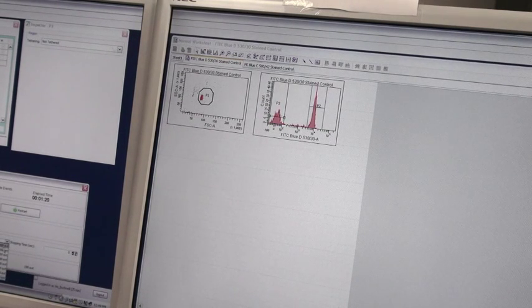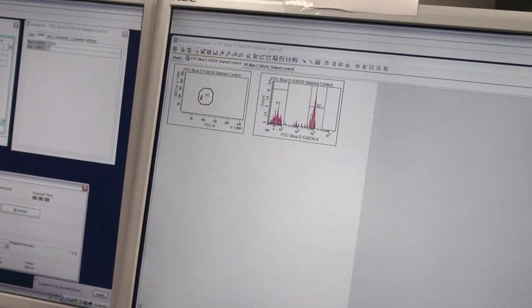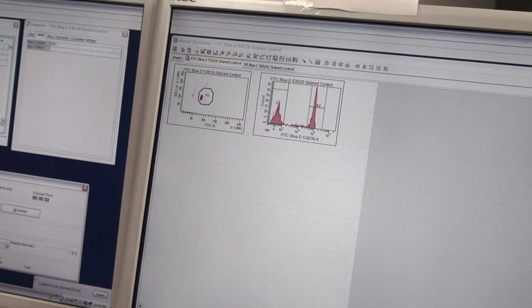Now that we've identified the positives and negatives, we're going to collect 10,000 events before we move on to our next tube, PE.